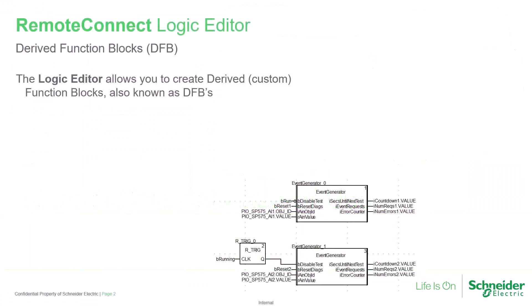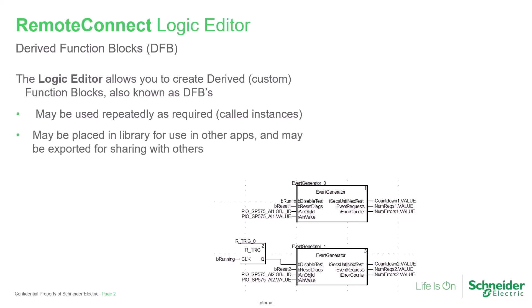When using Remote Connect with an X70 type SCADAPack, the Logic Editor provides the ability to create derived or custom function blocks, also known as DFBs. These can be repeatedly used wherever desired in an application. Each usage is called an instance. They may be placed into a library for use on other projects, and they can be shared with others as well.